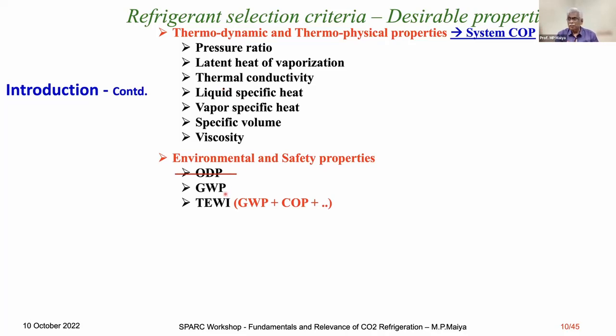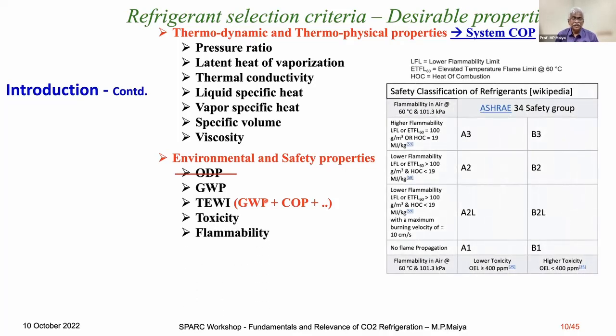But global warming potential is there. We have to look into TEWI, the total equivalent warming impact. Both GWP and COP come together. Then there is toxicity and flammability. Only carbon dioxide is A1, non-toxic and non-flammable. That is carbon dioxide.